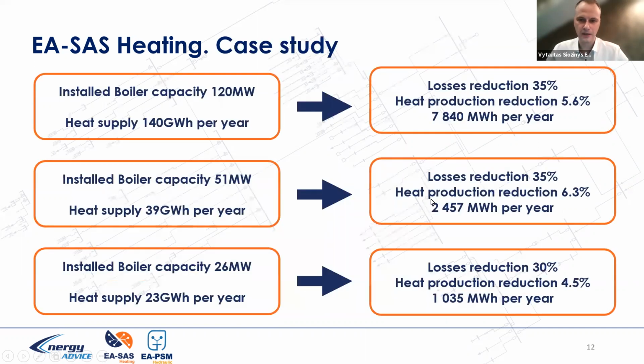So, a couple of examples about the savings in our portfolio. Installed boiler capacity is 120 megawatt for the city, and heat supply 140 gigawatt hours per year, and we have already reduced losses by near 35%. So heat production was reduced by near 6%. It's 7 gigawatt hours per year. You can assume that we increased the overall efficiency of a grid, calculated from energy delivered divided by primary fuel. We increased efficiency by 5%, or just reduced energy generation.